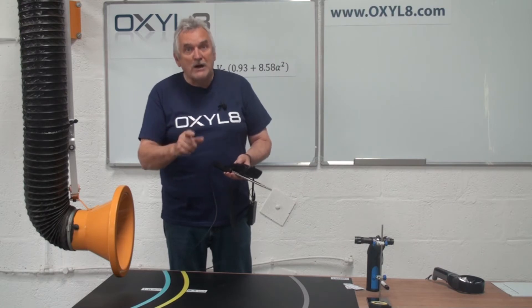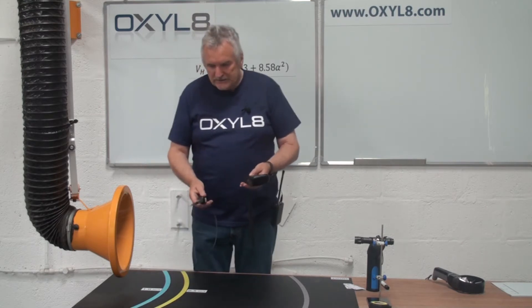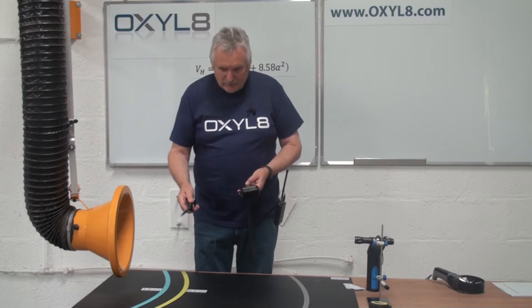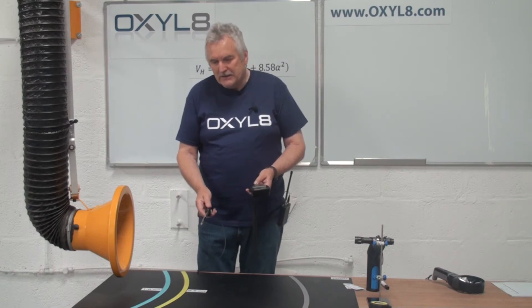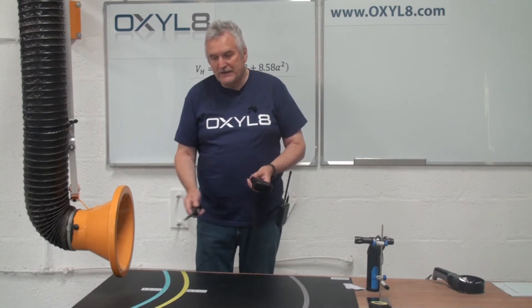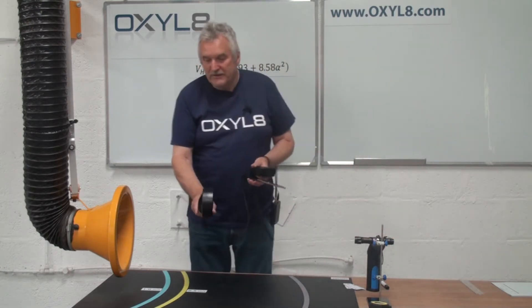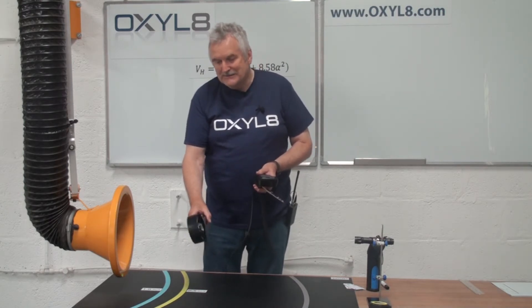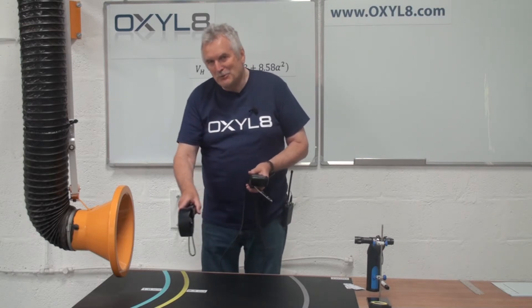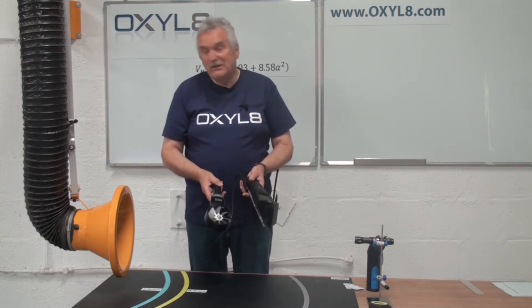So how are we going to measure those? Are we going to hold it on the center line? If you can see, there's a little laser shining on the center line here as we speak. Are we going to come out? Now what I've done, I've done this earlier today, and the error margin once we come away from the entrance is quite significant. And it's the same error margin with these 0.5 meters per second, the vanes are not turning terribly fast. The velocity may be coming predominantly from an angle. Measuring out here can be done, but I really don't recommend it.